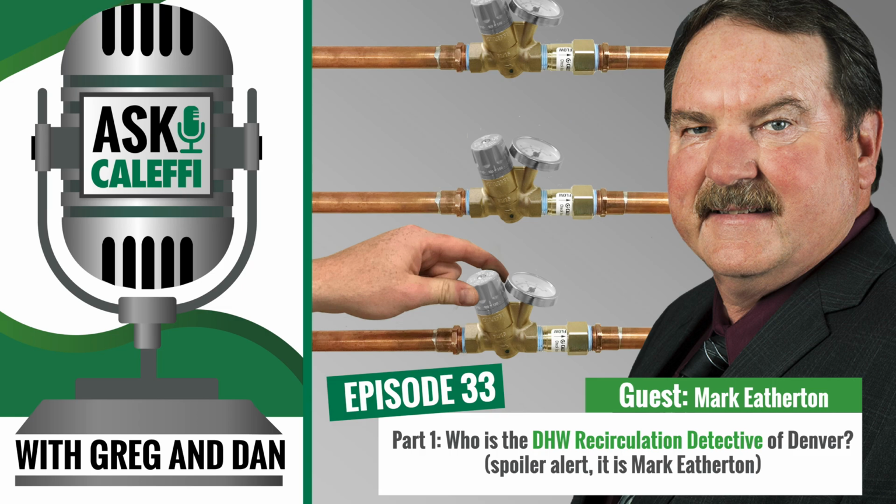So the first thing that happens when somebody complains about a problem is they put in a bigger pump. Right. Well, if a little pump did a little good, a lot of pump will do a lot of good. Oh, yeah. More cowbell. And it compounds the erosion problem. You start bringing more leaks on more of the returns. Right. And the complaints subsided a little bit, but it's still an issue.